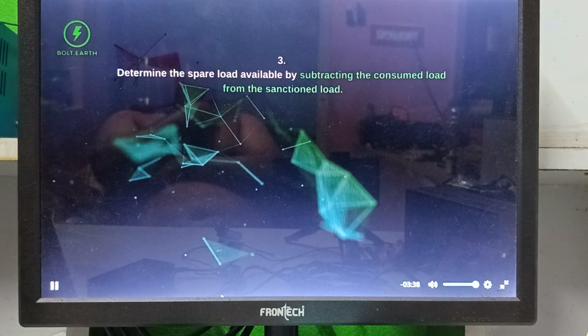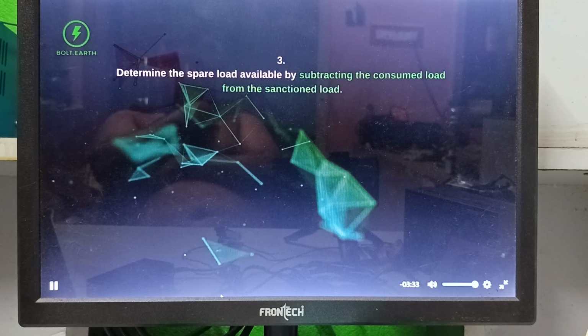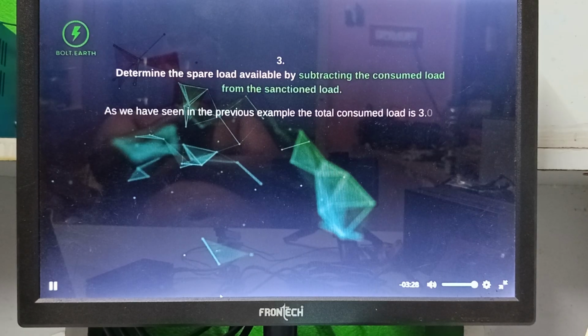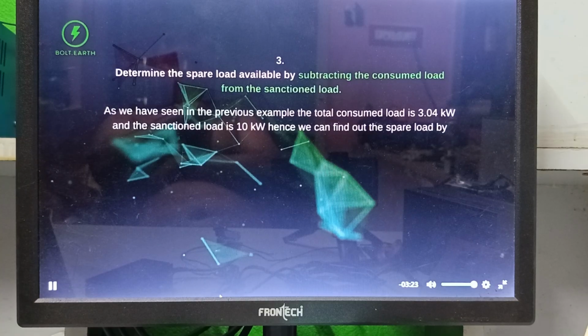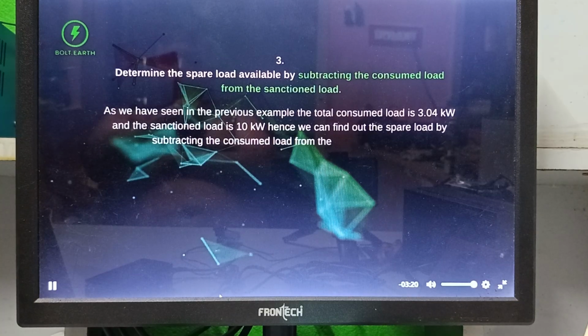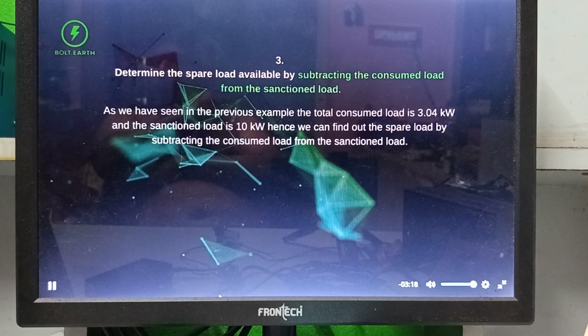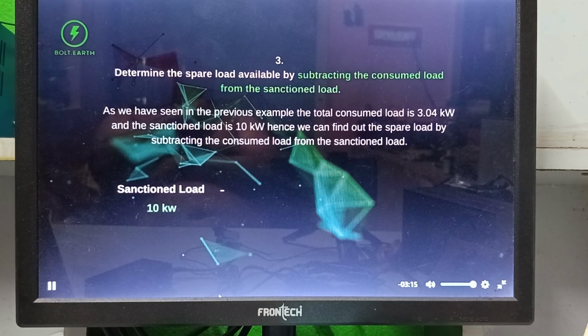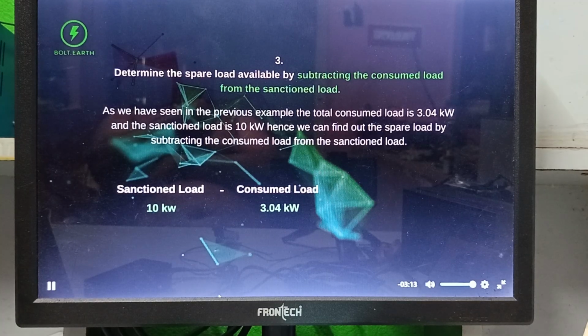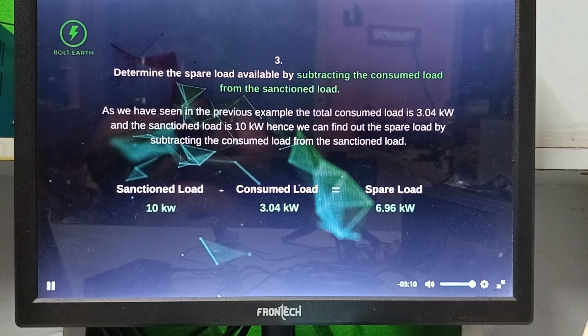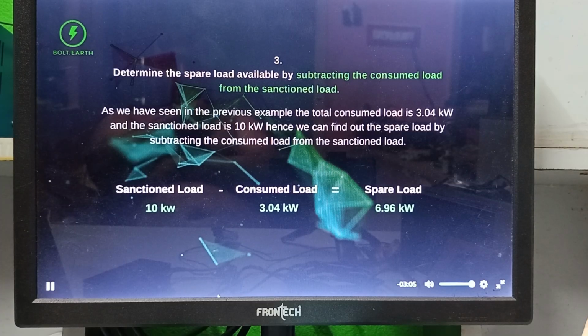Determine the spare load available by subtracting the consumed load from the sanctioned load. As we have seen in the previous example, the total consumed load is 3.04 kilowatts and the sanctioned load is 10 kilowatts. Sanctioned load 10 kilowatts minus consumed load 3.04 kilowatts is equal to spare load 6.96 kilowatts. As we have sufficient electrical load available, we can proceed with charger installation.